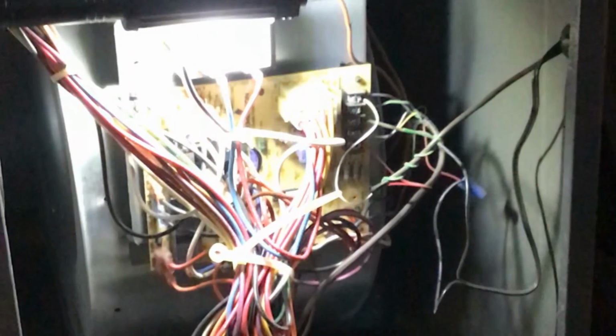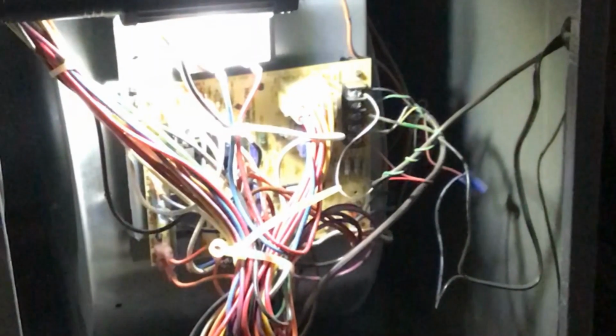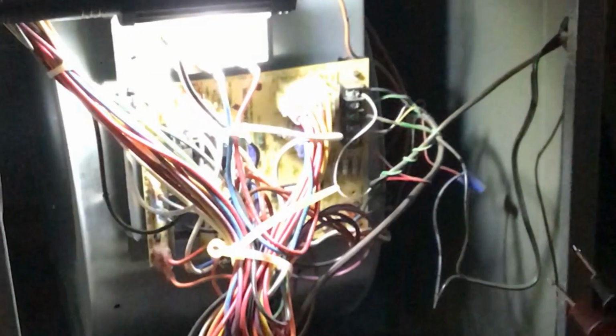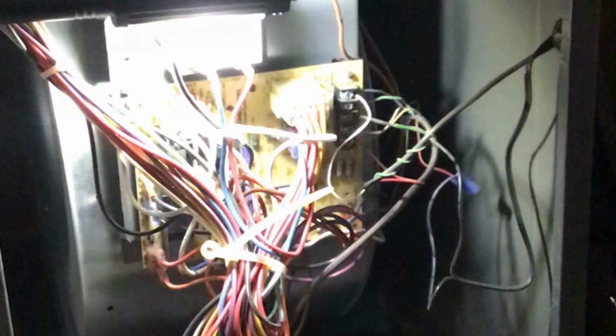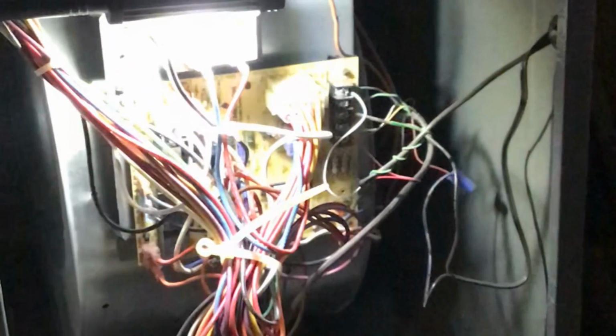In the beginning of the last segment, I talked about checking the contactor and seeing if you had 24 volts across the contactor. So let's assume that when we were outside, we did not. This is going to sound weird, but it's all going to make sense in the end. Just because you don't have 24 volts to your contactor doesn't necessarily mean you have a 24 volt problem. It could still be a 120 volt problem.